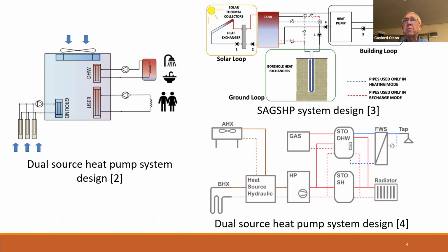Reference 3 comes from people in Italy. It was designed primarily for cold climates. And this does not have an air source mode. It's got solar thermal. And so there's a buffer tank that the solar thermal collector feeds into. And that in turn feeds into a heat pump to the building. But not only that, they've got 1 or more boreholes that are part of the system, which makes it multi-source.